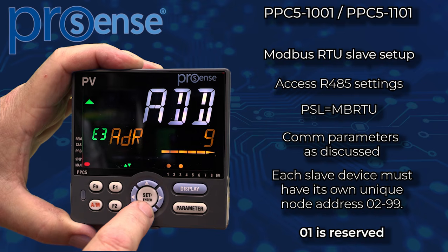Assign unique addresses to each serial device, 02 through 99. Do not use address 01. It's reserved and can cause conflicts.